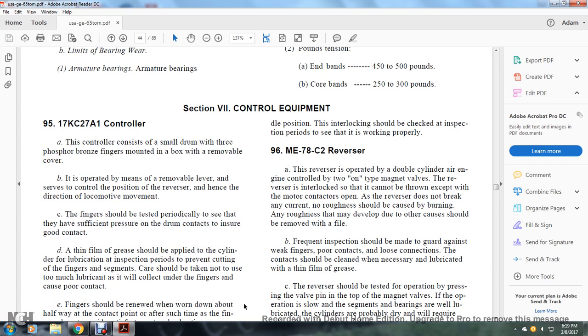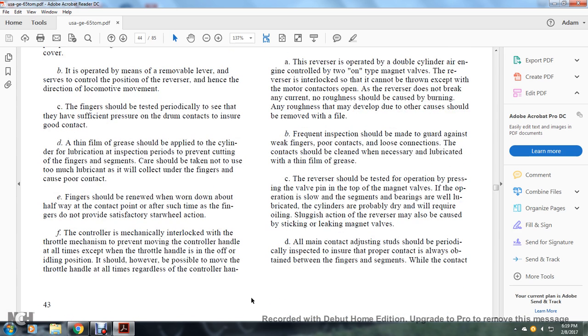Section 96, ME-78-C2 Reverser. The reversor is operated with a double-cylinder air engine controlled by a two-position on-type magnetic valve. The reversors interlock so they cannot be thrown except when the motor contactor is opened. The reversor does not carry any current. No roughness should be caused by burning, and any roughness due to other causes should be removed by file. Frequent inspection should be made guarding against weak fingers, poor contact, or loose connections. The contacts should be cleaned and lubricated with a thin film of grease. The reversor should be tested for operation with pressure at the magnet valve. Sluggish action may be caused by sticking or leaking magnet valves.